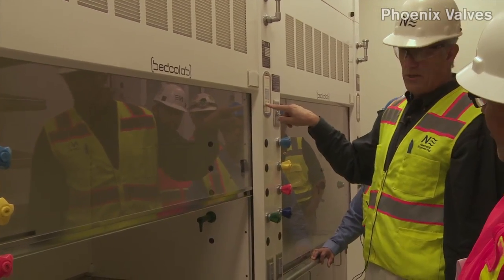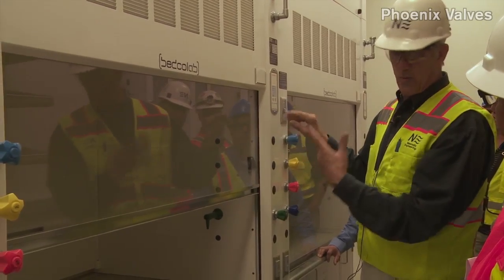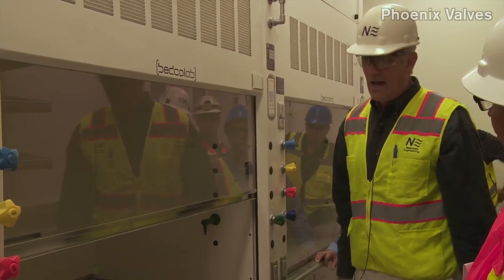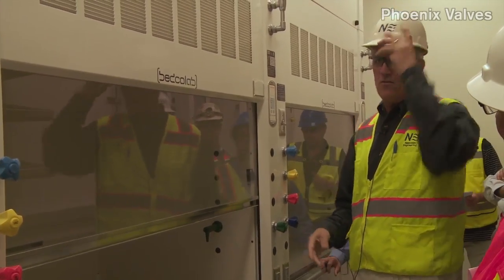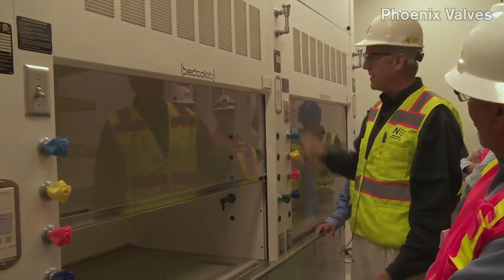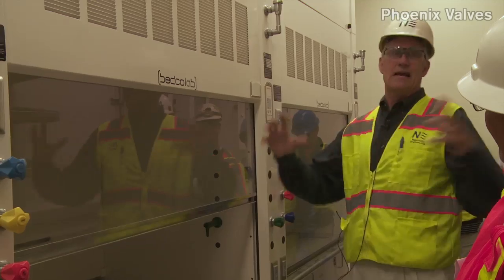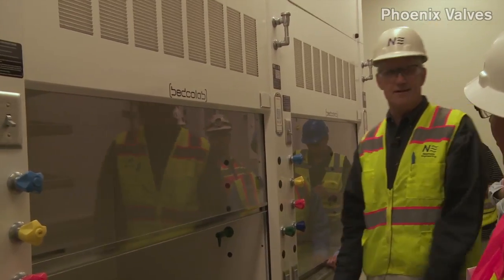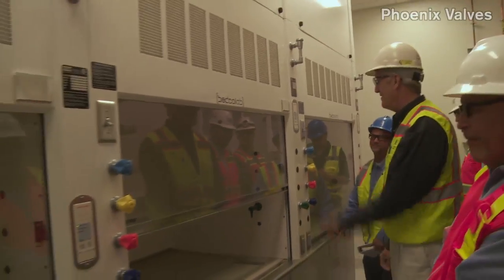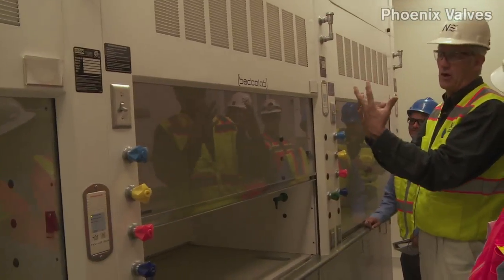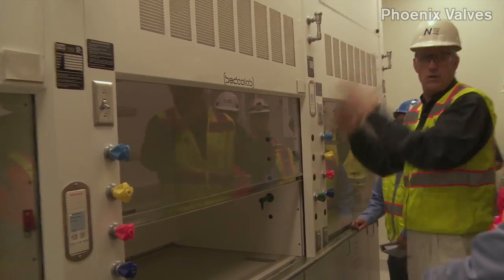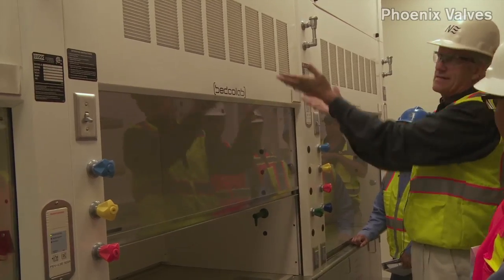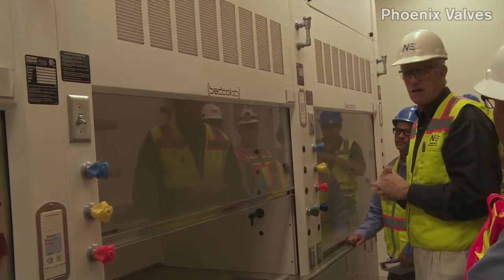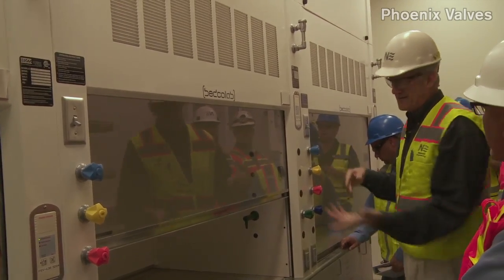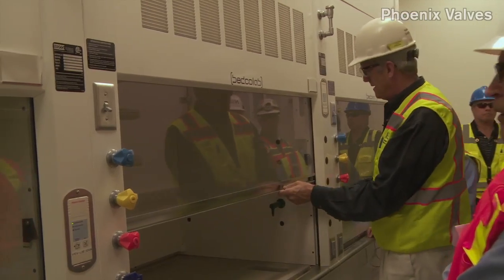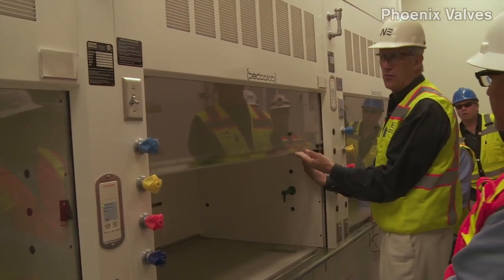The second alarm is called an emergency exhaust button. You push that, and it will also beep. You release it. What does that button do? Absolutely nothing. On a VAV hood, it would do something. We keep it on this hood, but it doesn't do anything other than beep and cause a red light. So if someone pushes the emergency, they may say, my hood's in alarm. It's push to set, push to release. There, you're a hero. On a VAV system, what that will do is bring you full flow regardless of sash position. Increase the flow? Increase. It'll increase it to maximum, but this is already set up at a constant volume where they want it to be, so that doesn't change anything on a constant volume hood. We didn't want to build two monitors, so we just built one. So again, if they defeat the sash stop or if they push that button, you'll get a red light and a slow beep.